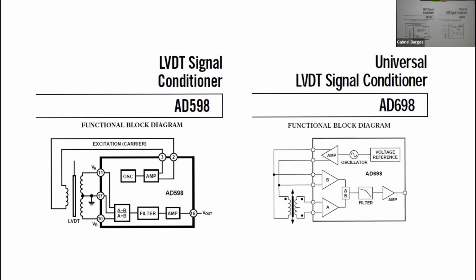If it worked — the problem is it didn't work, because all the aerospace LVDTs are done in that manner, where the sum of the secondaries is constant. But many industrial LVDTs you could buy commercially were not constant sum. If you put it together in a ratiometric operation like this, you might have an LVDT whose specs are plus or minus 0.25% of full-scale linearity, put it into this circuit, and now it's plus or minus 2% of full-scale linearity.